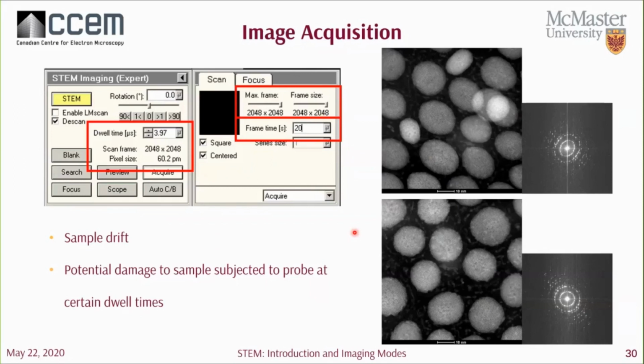Additionally, the acquisition of your image runs top down, scanning from left to right and from top to bottom. That means you're not acquiring a static image, but rather an image generated over a given amount of time. So the regions at the bottom of your frame were acquired a fraction of time later than what was acquired at the top. The most apparent artifact that you could see in your image is sample drift.